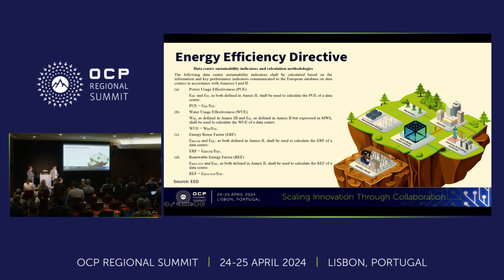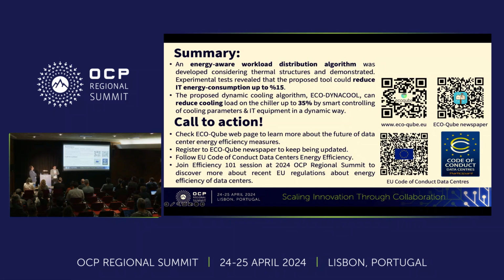So the main takeaways of this presentation: yes, monitoring data centers and IT elements like compute elements makes a difference. And if you monitor it well, the minimum energy gains is around 15% on the IT side. However, if you combine this IT efficiency with a holistic methodology, and combine it with the hardware components of the system, especially the cooling, your systems can, instead of simply cooling the environment, understand the cooling requirements of the IT equipment and optimize the cooling efficiency as well.